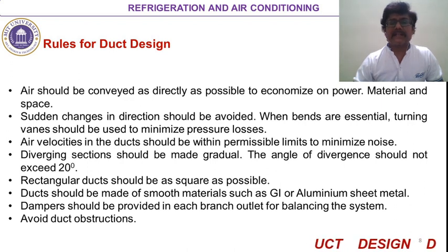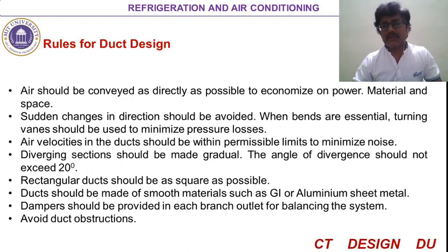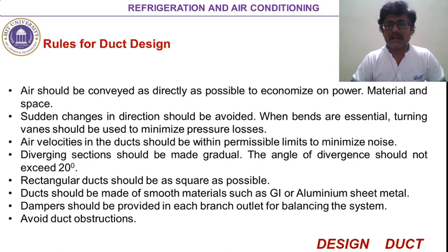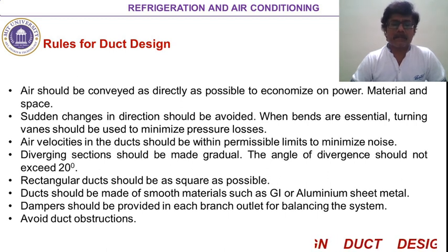Sudden changes in direction should be avoided, as we have discussed in the earlier discussion. Whenever bends are essential and unavoidable, turning vanes should be placed in the ducts so that we can minimize the pressure losses. Air velocities in the duct should be within permissible limits to minimize not only the noise but also the losses due to friction.